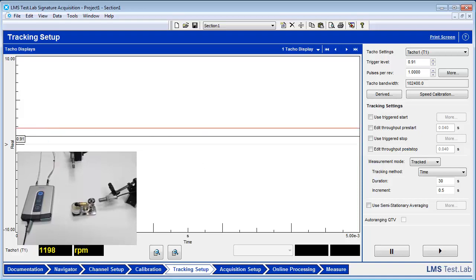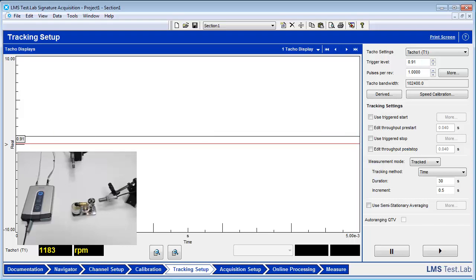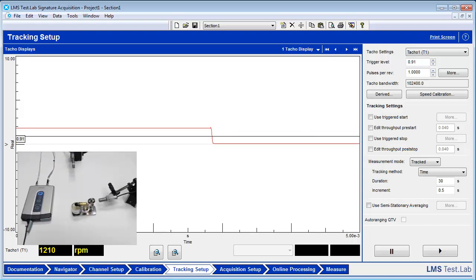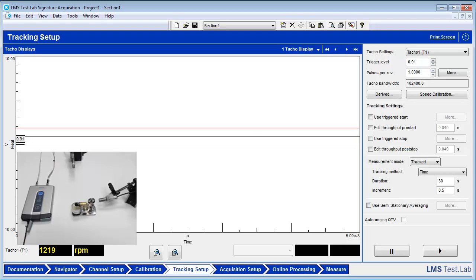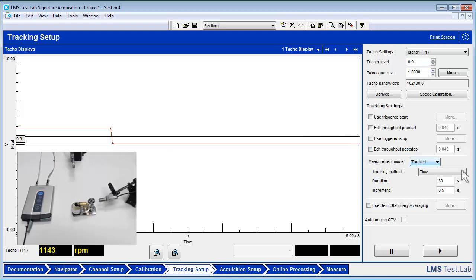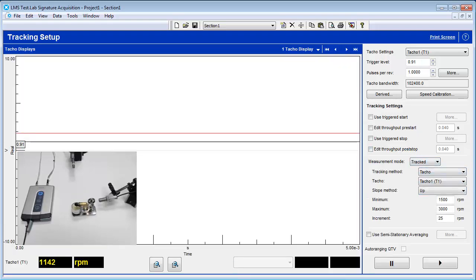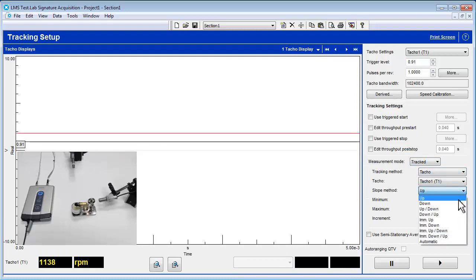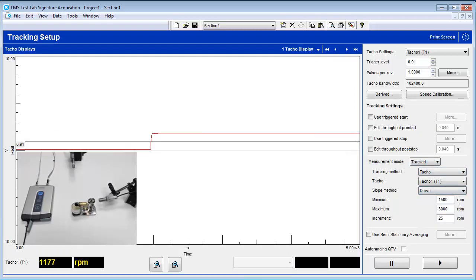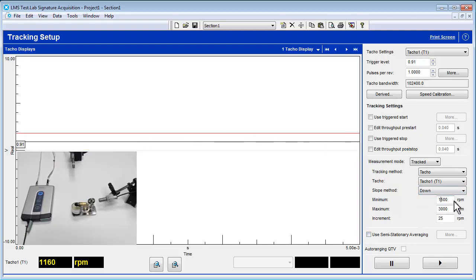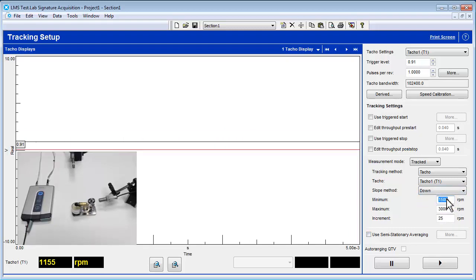There are multiple options for measurement modes, which include tracked and stationary. Tracked should be used when measuring a run-up or a run-down. Stationary should be used for a steady RPM. Set the measurement mode to tracked, because in this case we will be using a run-down. Set tracking method to tacho, and then change the slope method to down. For this Stirling engine, we will change the minimum to 300, the maximum to 800, and the increment to 2.